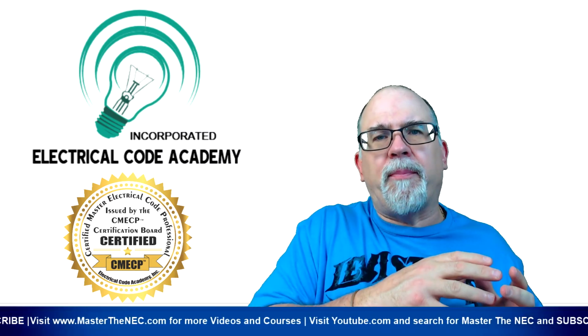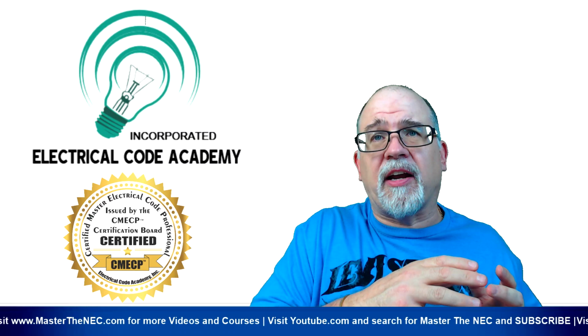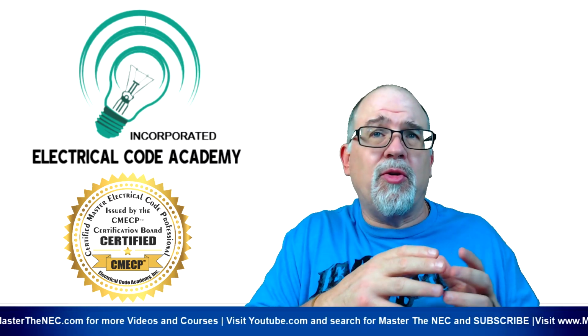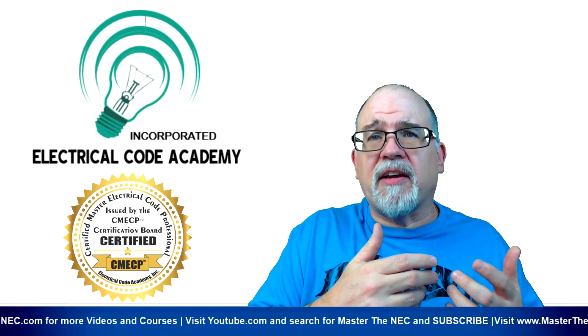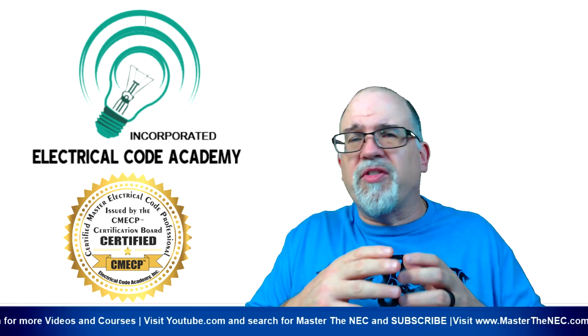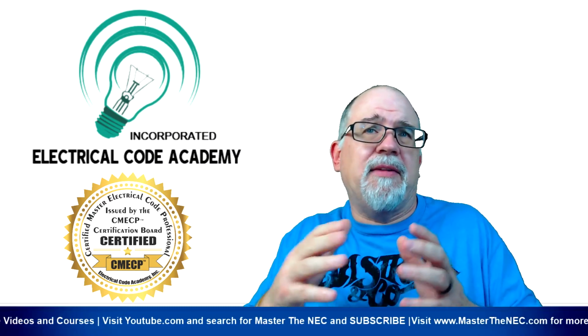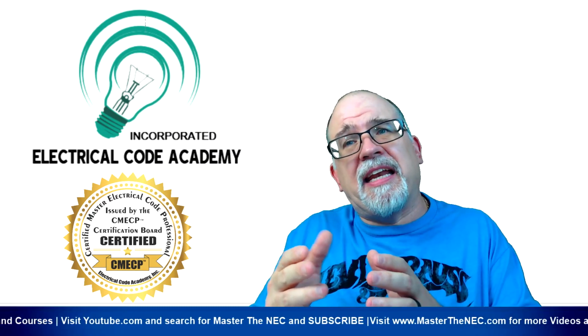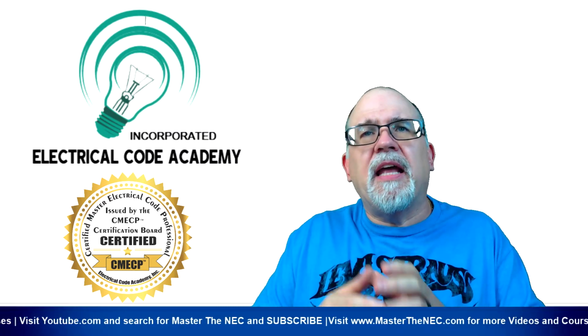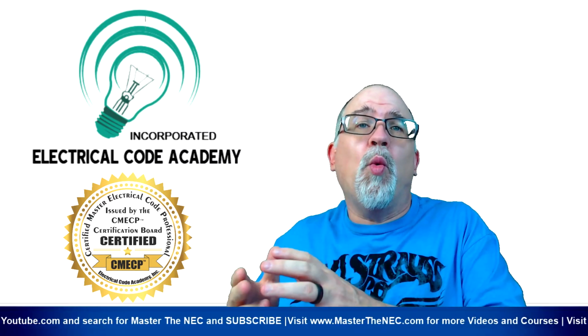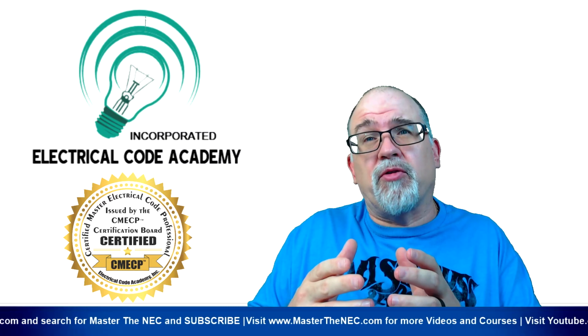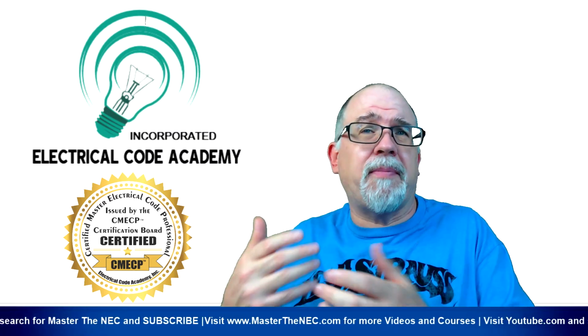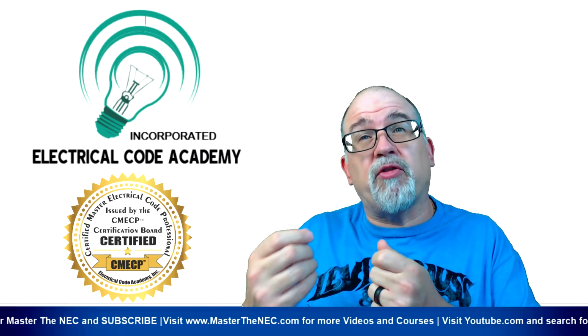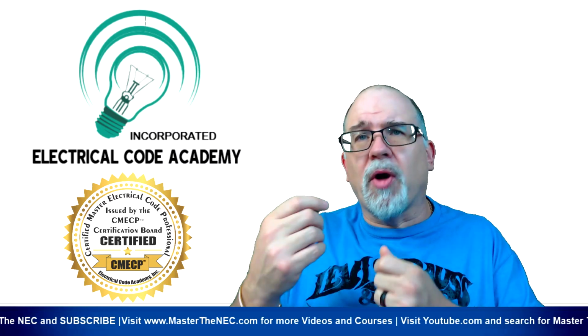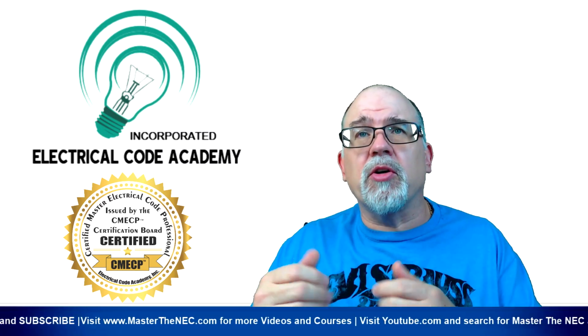We learned back in part 1 how to determine the primary current and secondary current of a transformer. Part 2, we learned how to do the overcurrent protection of the transformer, sizing conductors in part 3 and 4. Right now, we got into grounding and bonding, the basics. In the next one, we're going to go over what you do to actually size that transformer. So we have to balance the loads in the panel. We have to balance the transformer windings so we don't burn them up. We have to size all those.